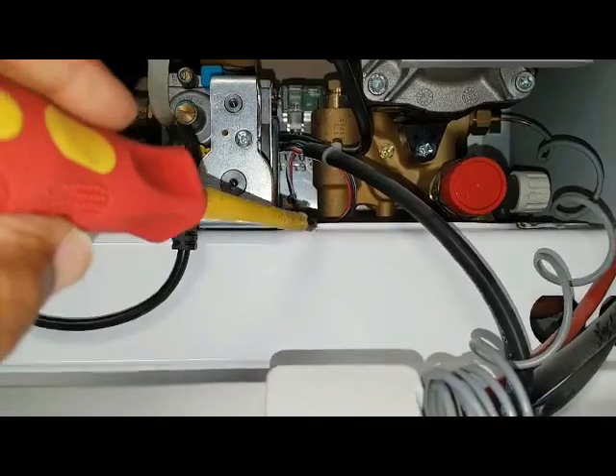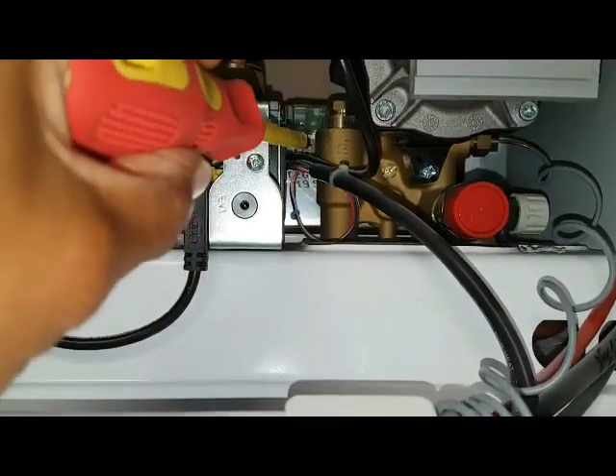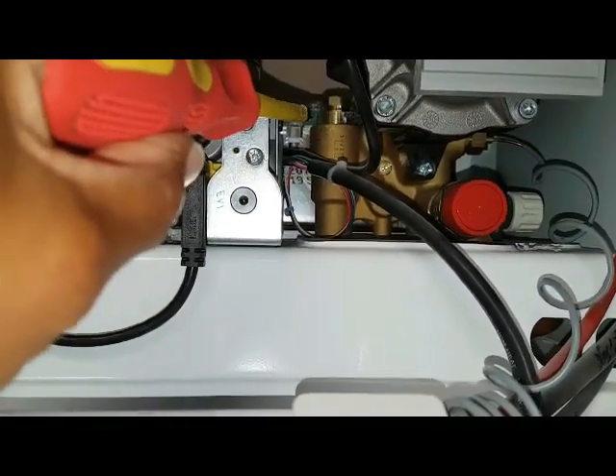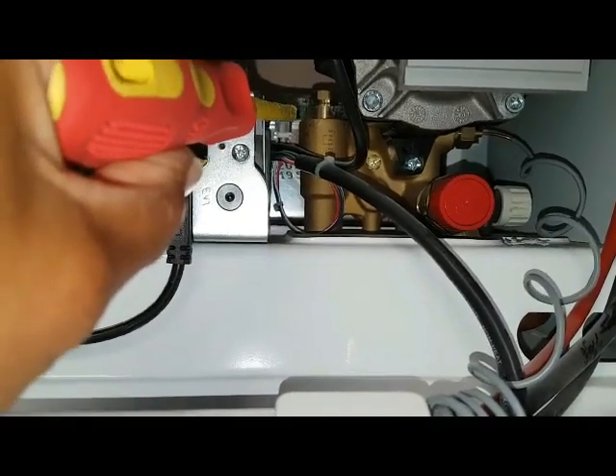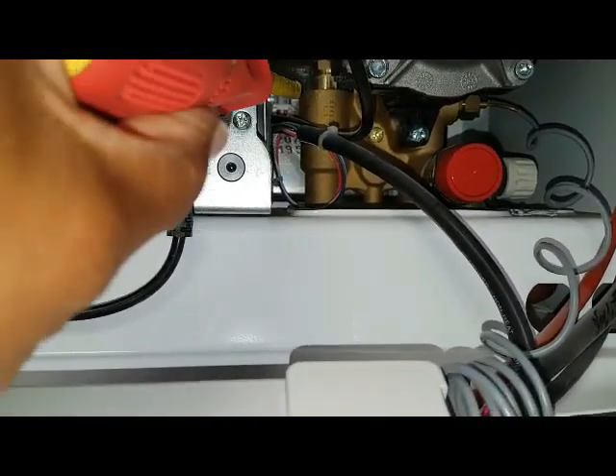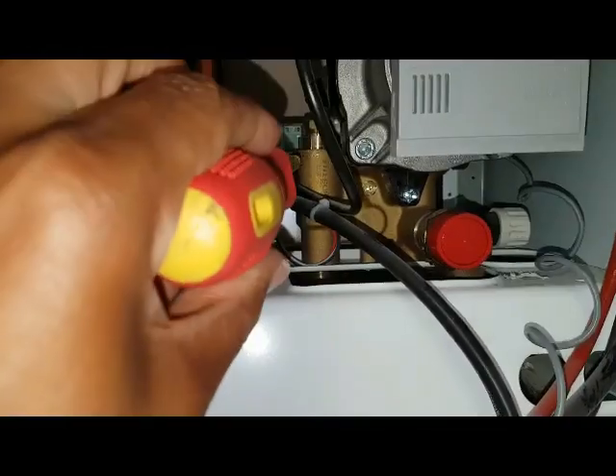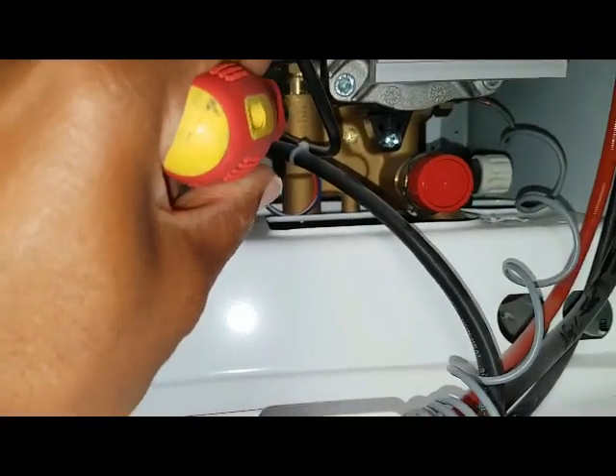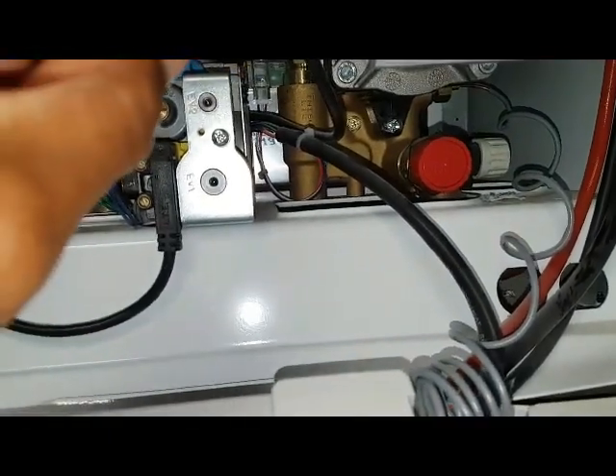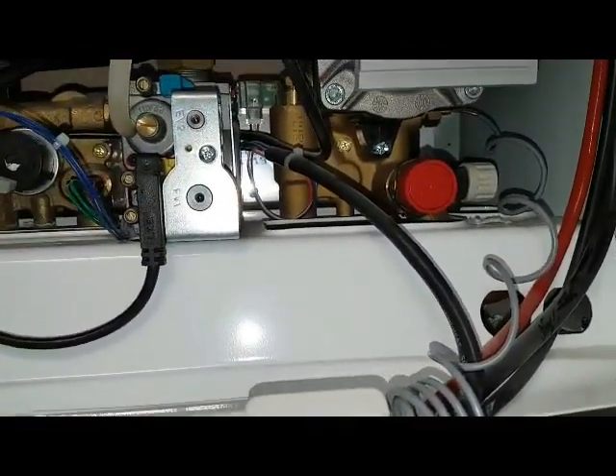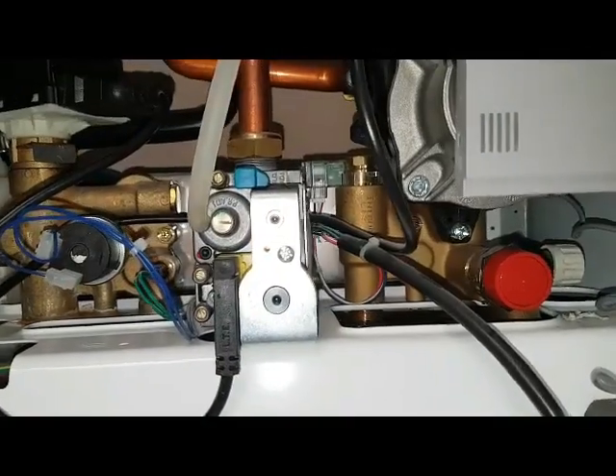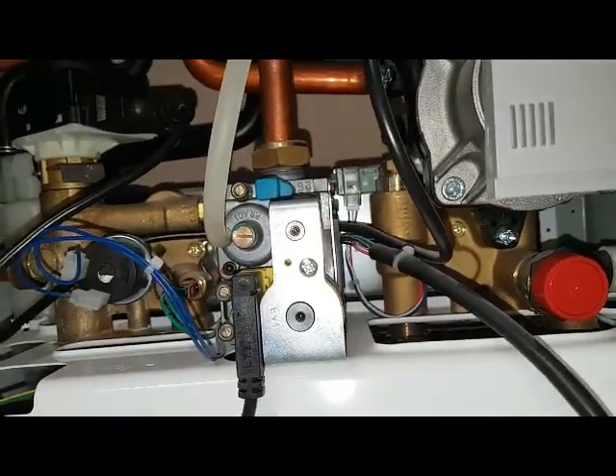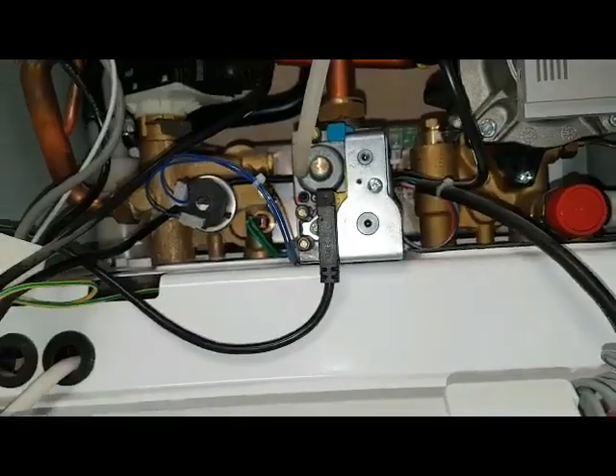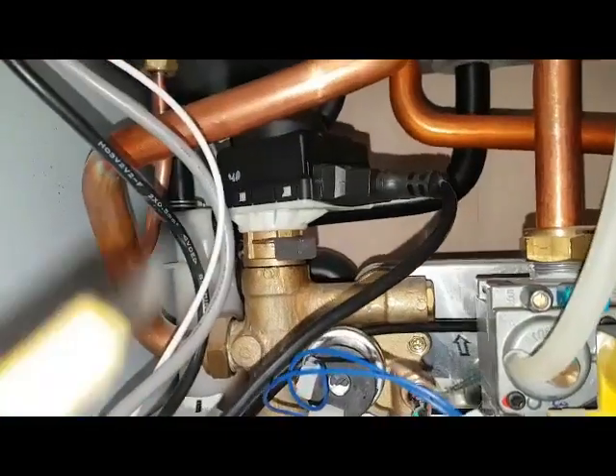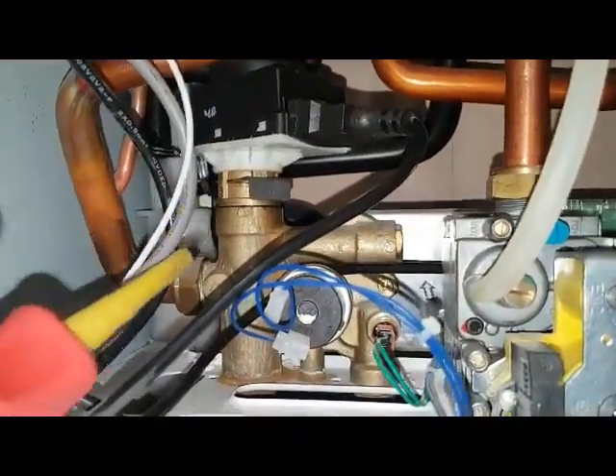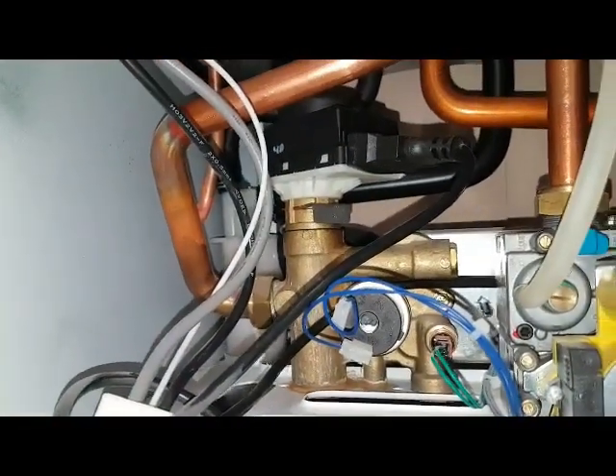So the cold water goes through the flow turbine, yeah? Rotates the flow turbine, as I said before. Creates a voltage. At the same time, that cold water then goes into the plate heat exchanger, up and in. When that voltage is generated through them wires there, it goes to the board. The board then tells the diverter valve through the actuator to shut off the central heat return.